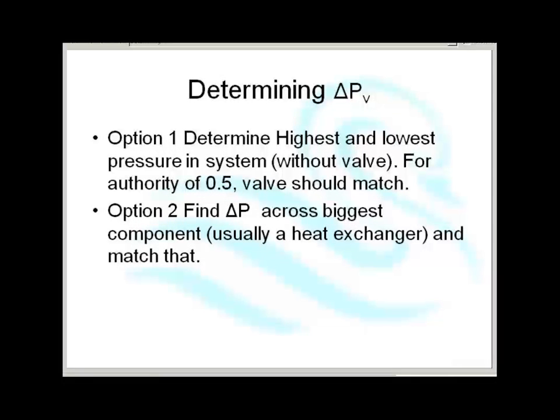Now, when we're sizing valves, the rep is going to ask us a couple of questions. He's going to ask us what the flow is. That's easy enough to find out. We just go and ask the operations people. This is for a system that doesn't exist. The other thing he's going to ask us is, what is the pressure drop across the valve? Well, I don't know. So there's a couple of ways of working out what the pressure drop will be.